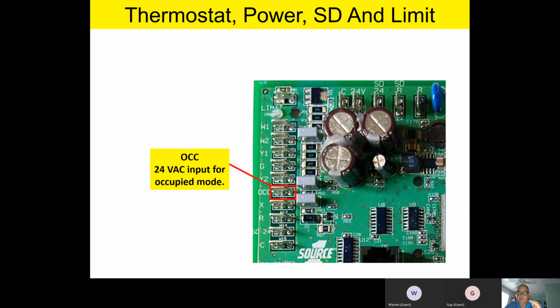So one of the things that I always encourage everybody to do is double check your line voltage. Double check your line voltage feeding the 24 volt transformer on the job site. And we always ship our transformers on the highest voltage they're capable of. So let's say it's a 240 volt system and it's got a 208/240 volt primary transformer tap on this unit. By the way, we always ship that transformer on the 240 volt primary tap. So you get on the job site and you find out that your actual line voltage is, say, 212, 213, or let's say 216, 217. The temptation would be, well, I'll just leave it on the 240 volt tap.